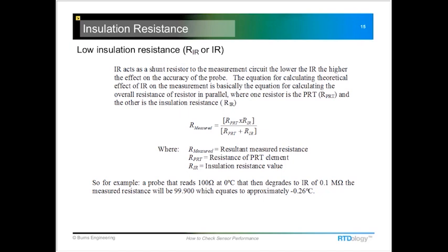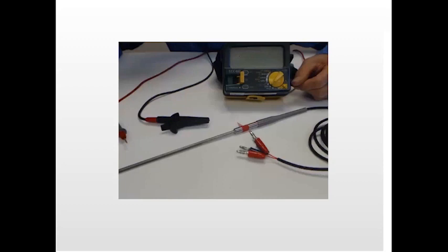If we look here at our example, we've got really, really bad insulation resistance of just 0.1 megohm. That's going to result in a quarter of a degree C error in our measurement. So that's pretty significant. But if that were up at that 1 megohm, this number is going to drop quite a bit, and you can run through the math there and check that. But anyway, I just wanted to show how we typically would do this test.